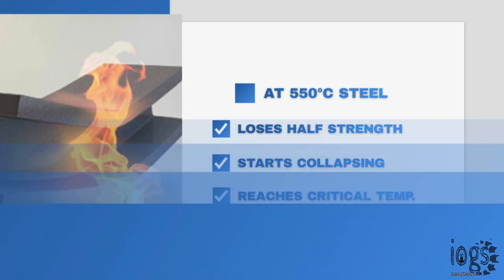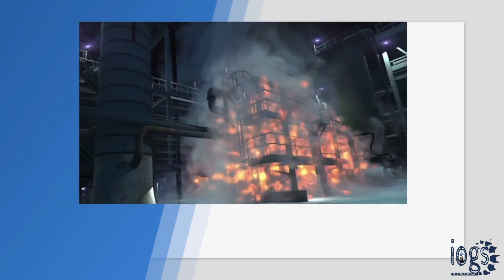The purpose of passive fireproofing in the industry is to retain steel integrity intact for a certain period of time and to prevent steel from collapsing prematurely. A fireproofed steel can withstand fire up to 240 minutes.